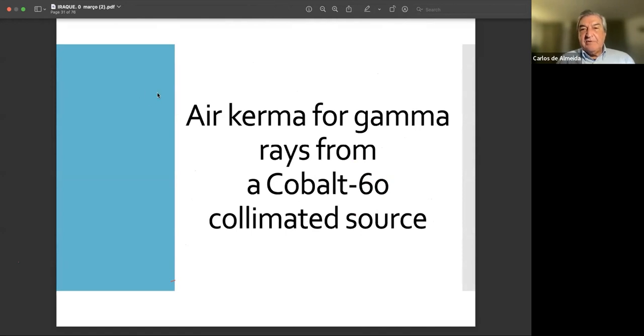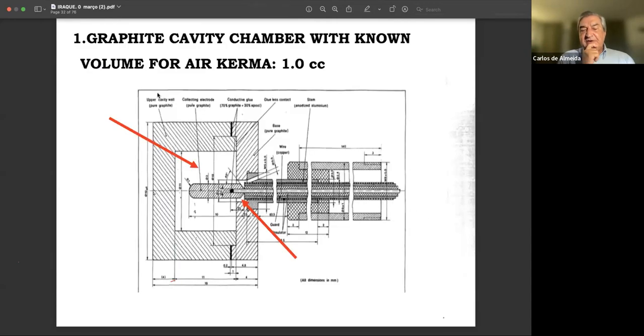Now, when we talk about the air chamber for gamma rays, for cobalt-60, which we have used for many, many years, the next slide shows the graphite chamber whose volume we know. This is the wall of the chamber. This is the electrode, which is the same material as the wall. This is graphite. Then you measure the volume without the electrode. You insert the electrode into the chamber, and you add this little portion of air, and then you have measured very accurately the volume of the chamber.